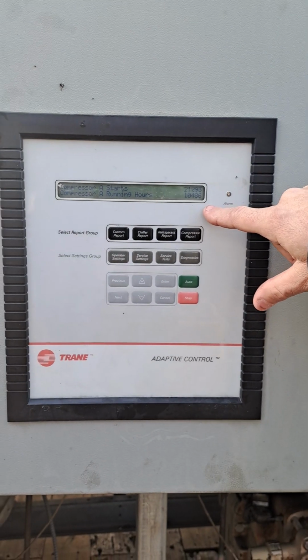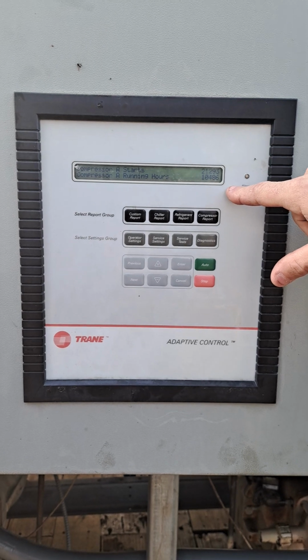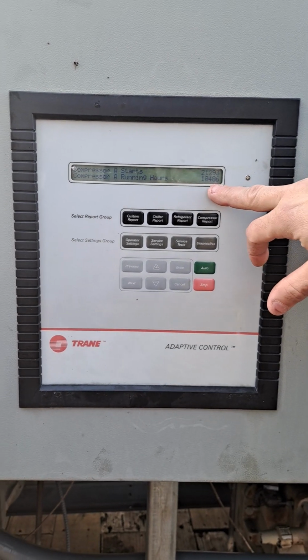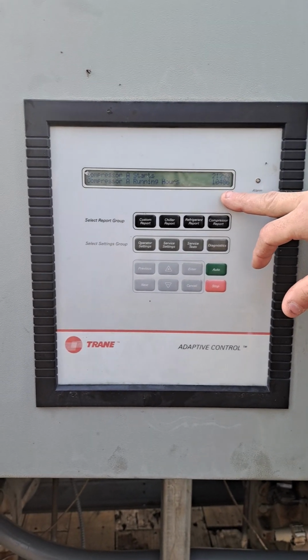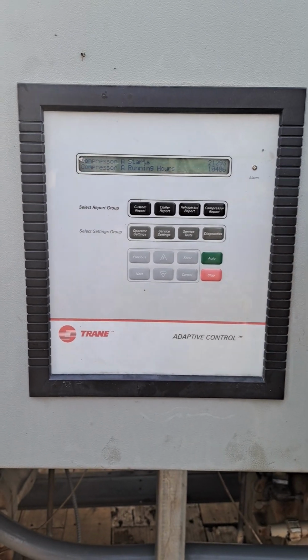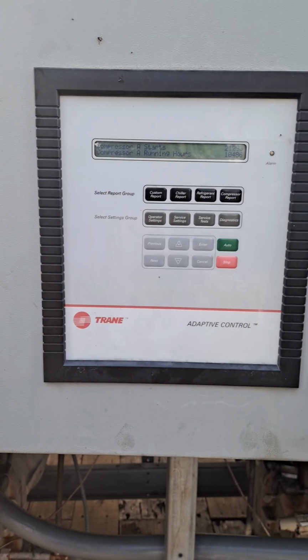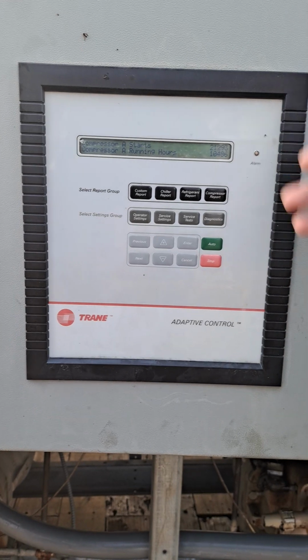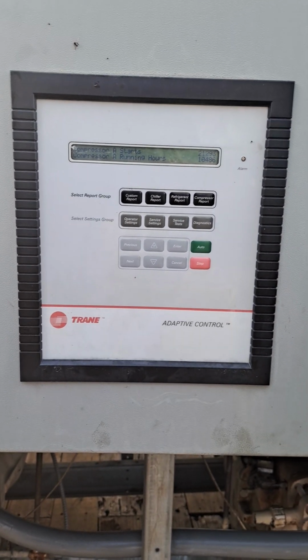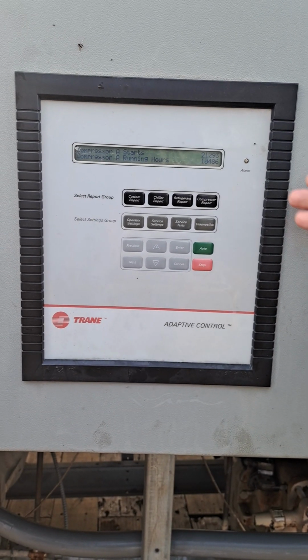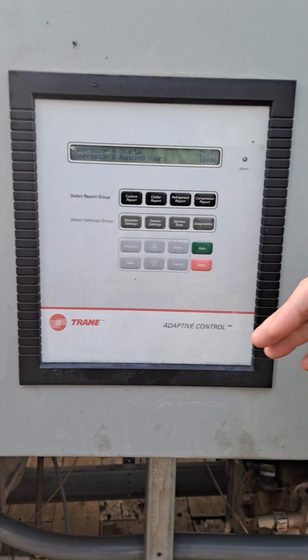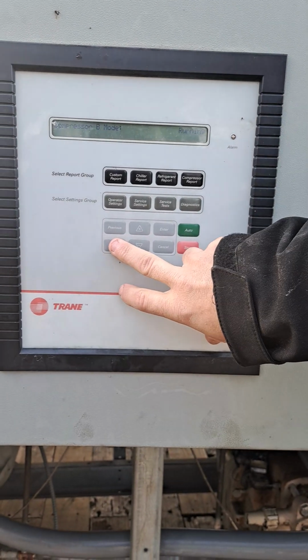It's possible that these are fairly new compressors. If somebody actually reset all this and that's accurate, these only have 10,000 hours on it. Right. And they're really quiet, so it's possible that's all they have on. So these things, you can run 100,000 hours on a screw compressor. So if that's actually the case, you guys probably got a decent machine. So if that's accurate, that's the thing.